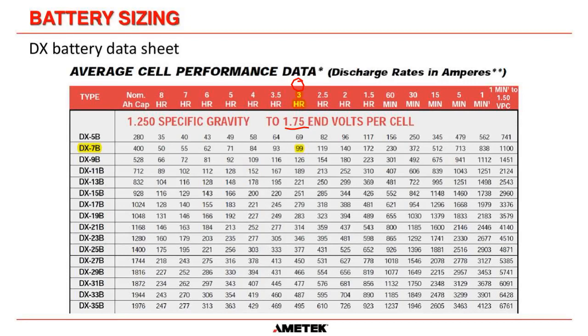So then we go to the left, to this column, and say, okay, in the previous slide we said we needed 86.6 amps of current out of the battery for full load. We can't use the DX5 here, because that only gives us 69 amps. But we can use the DX7, because it will give us 99 amps for 3 hours, which is more than 86.6 amps. You could go to the DX9, or any of the ones above the DX7 would work, but obviously the price goes up the more power you need. So the best solution for this 10 kVA UPS, which has 8 kilowatts at 0.8 power factor, to have a battery that lasts 3 hours, is the DX7B.